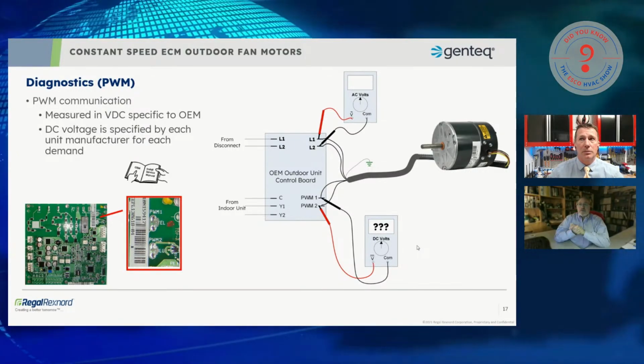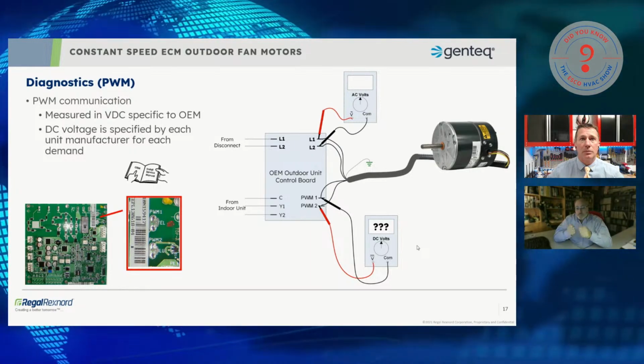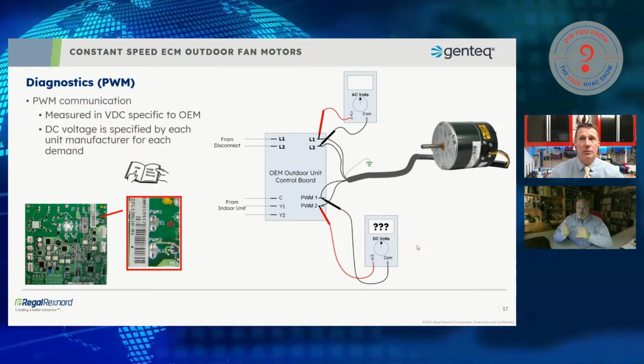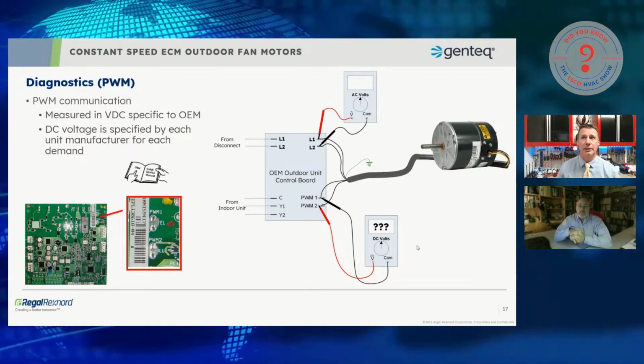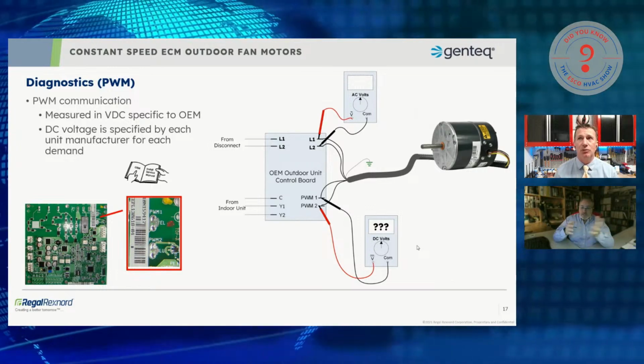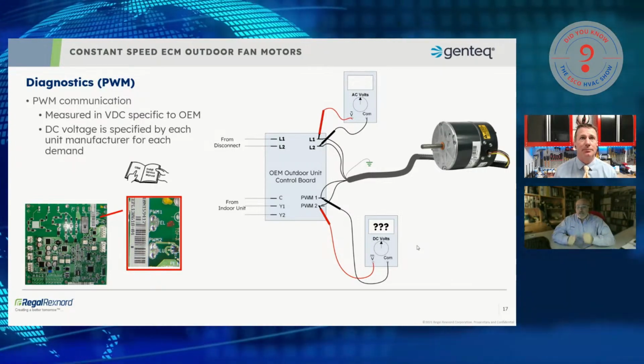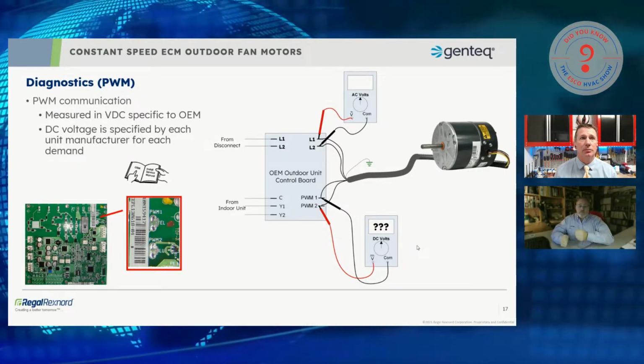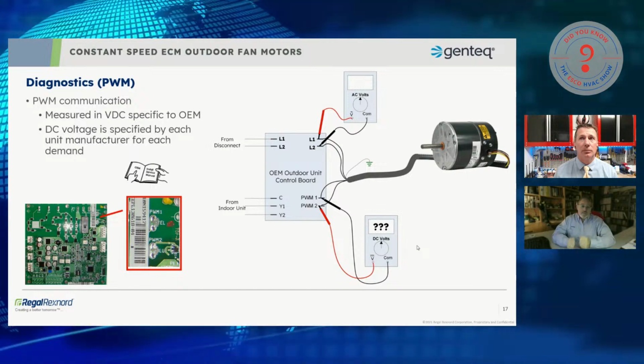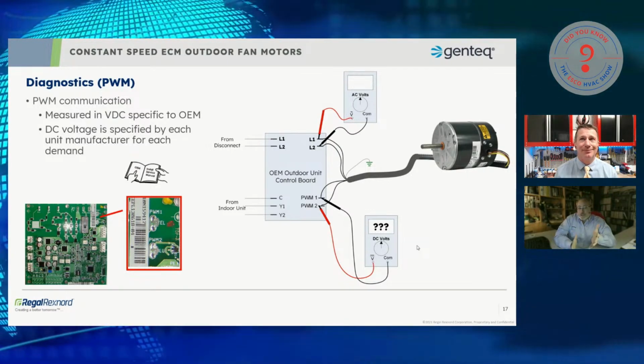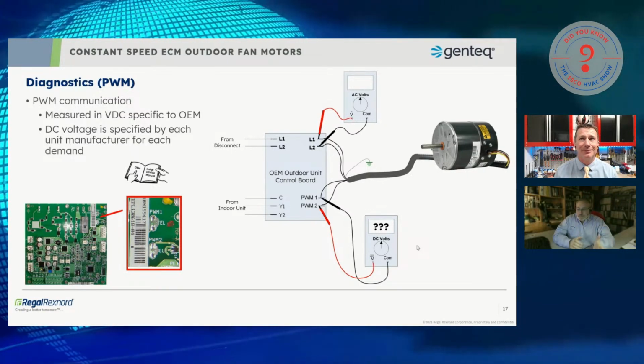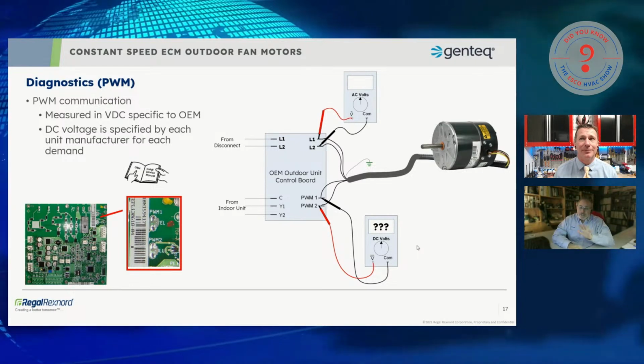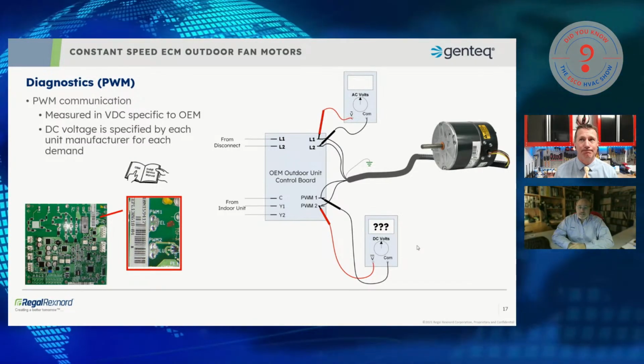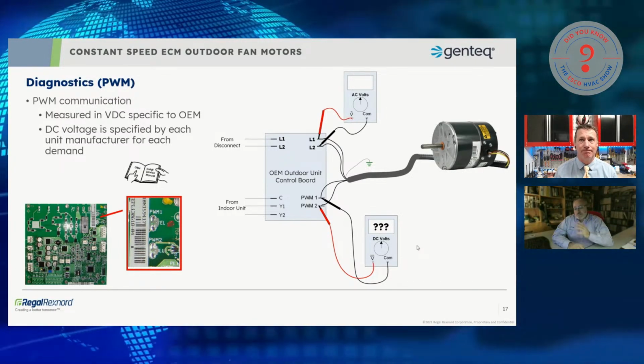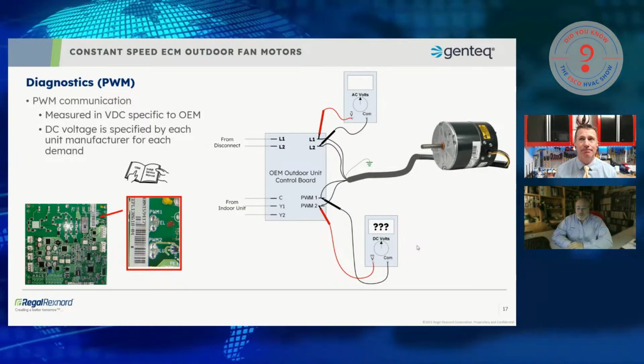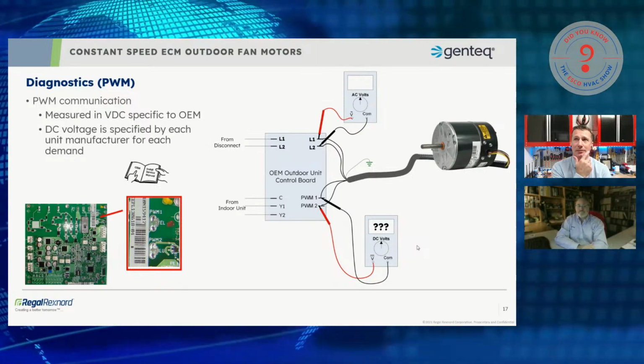I say that because you may get comfortable after you start measuring these, seeing say 2 point something DC for first stage and 3 point something DC for second stage, and then you'll go on one. You'll have 1.5 and think, well, that's not right. Something must be wrong, but the motor's running, and think, well, the motor must be bad or the board must be bad. It might just be a low ambient staging that it's in versus something actually being wrong with the motor or the control. Fantastic point.